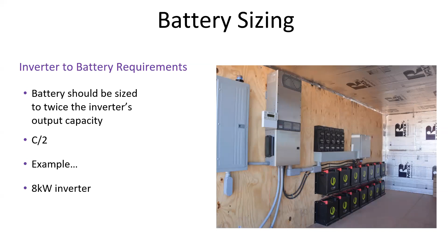Most of what that's based on is how the PV works, I know that's a confusing idea, but if you've done AC coupled systems you probably understand it. It's really based on what that battery-based inverter wants to see as far as how many inverters you need, or its limit as far as PV on the AC coupled array, as well as our output limitation, which is basically the C/2 guideline: the battery should be sized to twice the inverter's output capacity. You have to add more inverters just to cover the array, and then add more batteries. Whereas when we go with the DC coupled solution, the DC direct transfer switch solution, we're able to go with a smaller battery-based inverter.